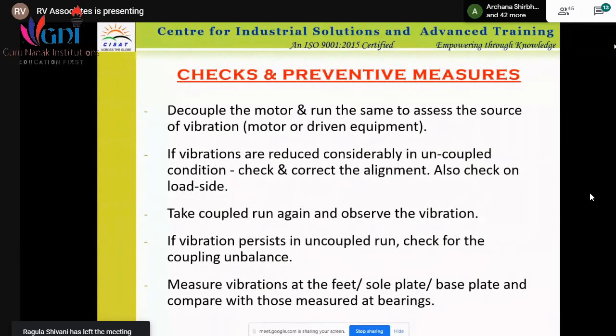So what do we do? There are always some predictive and preventive maintenance techniques. What we say is the identification of the fault. How to identify the fault? The first condition is very common. Whenever there is a problem in the motor, it will lead to vibration or a rise in temperature. So whenever we go to the site, we put our hand on the motor. It will give you two indications: first the vibration and second the temperature. If you are doing the same thing regularly, it's like a doctor, you know what temperature it should be and how much vibration it will give. So that is one of the best checks for fault identification.